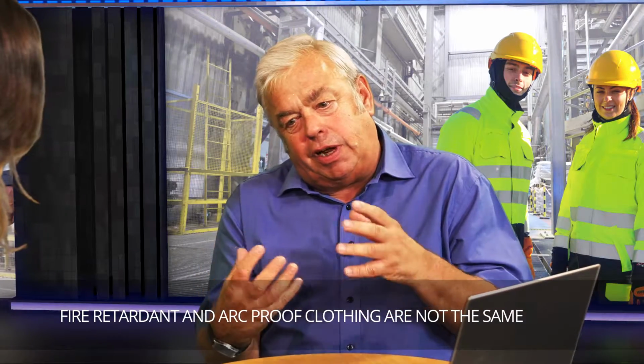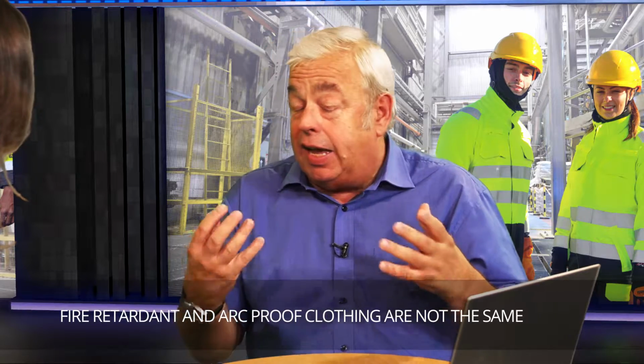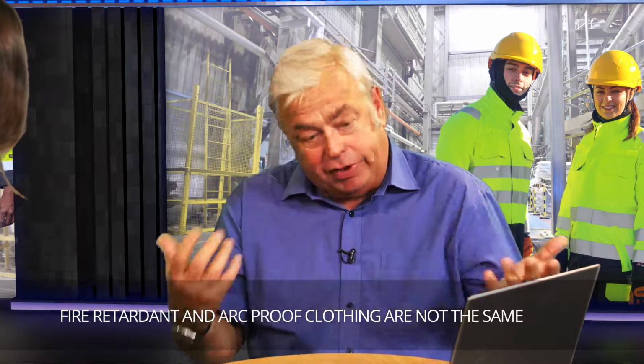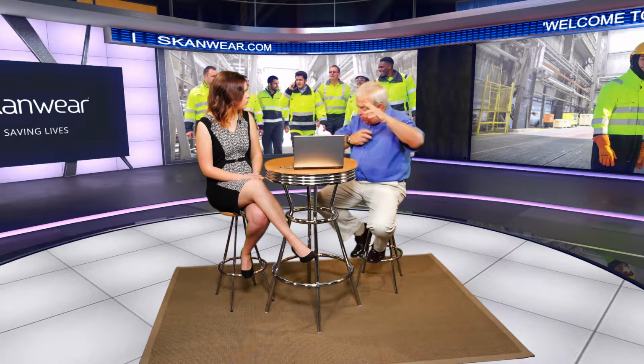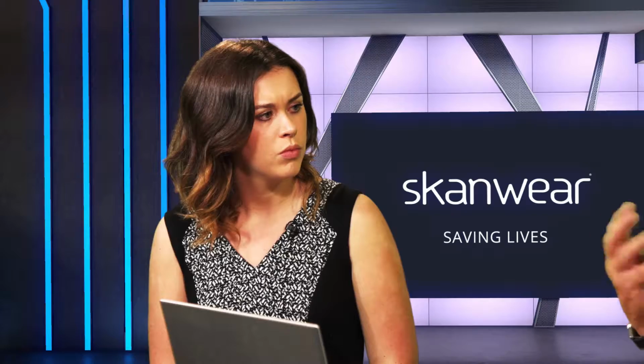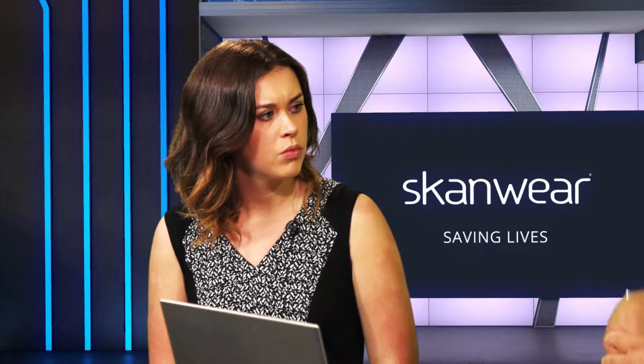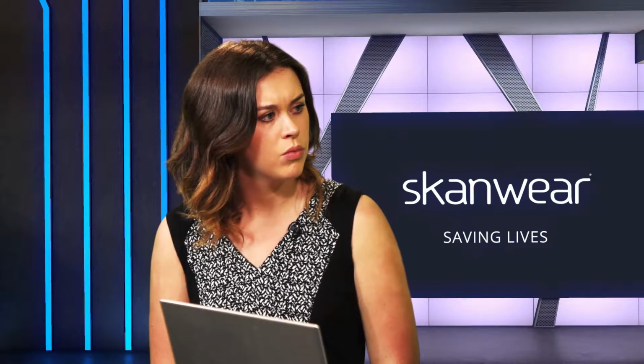Well, flame resistant clothing does exactly what it says on the can, it actually resists catching fire. Whereas arc proof clothing also resists catching fire, but it has thermal effects. So when the plasma ball comes out and all that thermal energy hits the person, it's actually stopped and it can't actually burn the skin. That's known as the Arc Thermal Performance Value, ATPV, for instance, and we'll come onto that a little bit later.